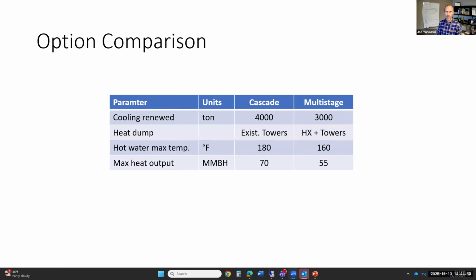Both can make hot water, but the Cascade option can make a little bit hotter water. We don't expect to need to operate at 180. We think we'll be able to operate at 160. It's still nice to have the flexibility. And the maximum heat output that we could afford with these two different types was higher with the Cascade. Early on, the utilization will be lower because only half the campus is converted to hot water. But over time, it will be more beneficial, and getting that in sooner saves costs down the road. So we ended up selecting the Cascade option.